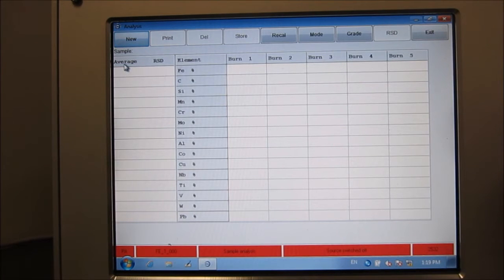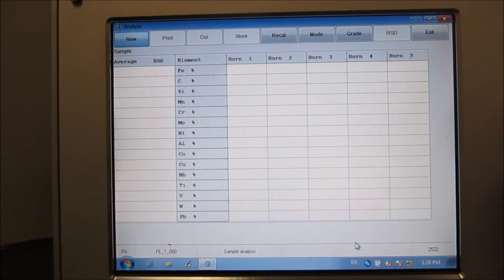Over here you'll have the column for the average value. Here is the relative standard deviation, the RSD. Once we start burning a sample or sparking, you'll see the results of the concentration for each element appearing here in percentage. And when you start burning a second one, it will appear here in the next column. Underneath here you will see that it is red because I did not turn on the source. Over here it will tell you the reason why it is red. It is like an error indication. So when I turn this on, you'll see that the red color will disappear.